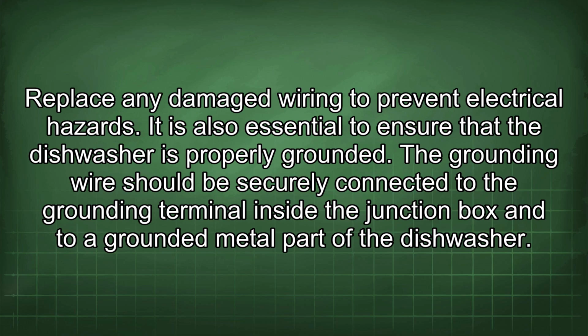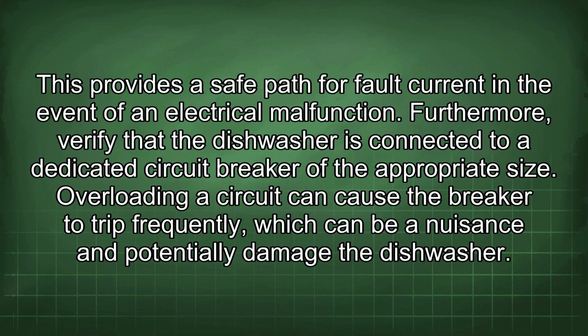The grounding wire should be securely connected to the grounding terminal inside the junction box and to a grounded metal part of the dishwasher. This provides a safe path for fault current in the event of an electrical malfunction. Furthermore, verify that the dishwasher is connected to a dedicated circuit breaker of the appropriate size. Overloading a circuit can cause the breaker to trip frequently, which can be a nuisance and potentially damage the dishwasher.